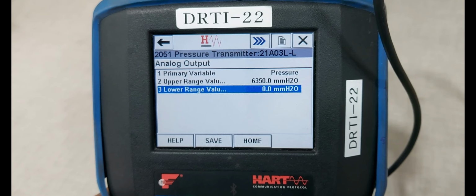Now multimeter is showing 4.003 milliamps. We are entering the same value 4.003. Then press OK. Field device output 4 milliamps equal to reference meter. Then select yes and enter. Set the field device output to 20 milliamps. Okay, then press OK.